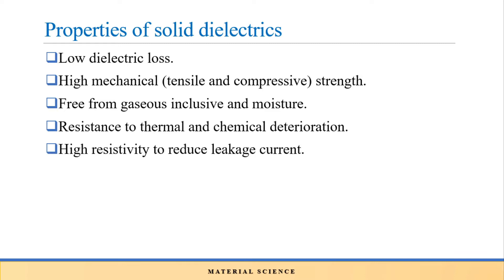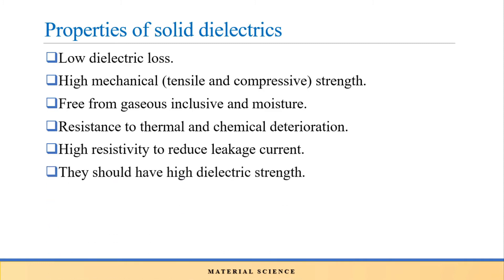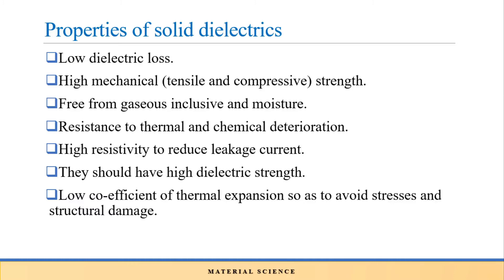Next property is high resistivity to reduce leakage current. If insulating material is provided over a conducting part, there is some leakage current flowing radially outward, and the function of the insulating material is to suppress that leakage current. Next, they should have high dielectric strength. After that, a low coefficient of thermal expansion so as to avoid stresses and structural damage.